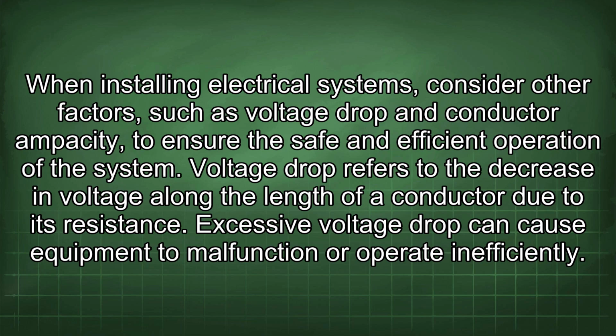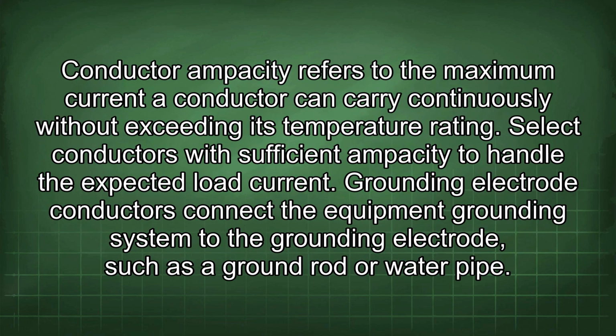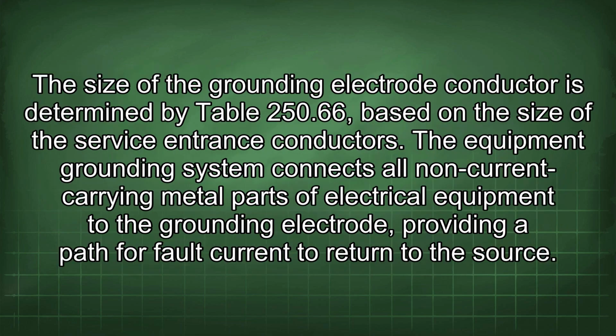Voltage drop refers to the decrease in voltage along the length of a conductor due to its resistance. Excessive voltage drop can cause equipment to malfunction or operate inefficiently. Conductor ampacity refers to the maximum current the conductor can carry continuously without exceeding its temperature rating. Select conductors with sufficient ampacity to handle the expected load current. Grounding electrode conductors connect the equipment grounding system to the grounding electrode, such as a ground rod or water pipe. The size of the grounding electrode conductor is determined by Table 250.66, based on the size of the service entrance conductors.